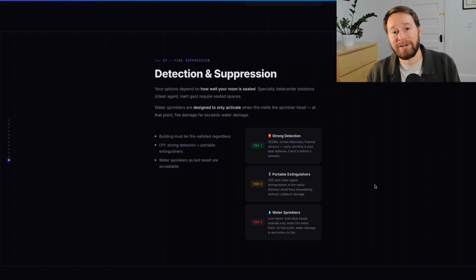Water sprinklers are allowed, which sounds crazy, but the logic is that if fire is reaching those sprinkler heads to set them off, any water damage to your systems is already being caused by that fire. So it's more about the safety of the building and the people in it than about saving your systems at that point.